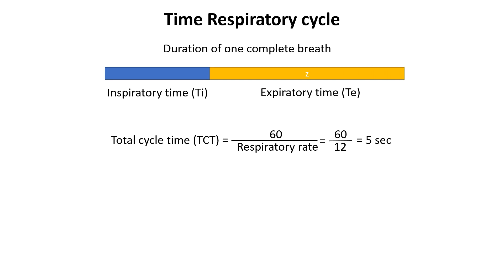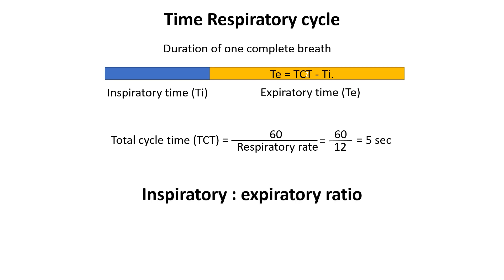This total cycle time is divided into inspiratory time and expiratory time. Inspiratory time is the duration of the inspiratory phase, and expiratory time is the time left for passive exhalation after inspiration. The ratio of inspiratory time to expiratory time is called the IE ratio and is commonly set at 1:2 or 1:3 to allow sufficient time for exhalation.